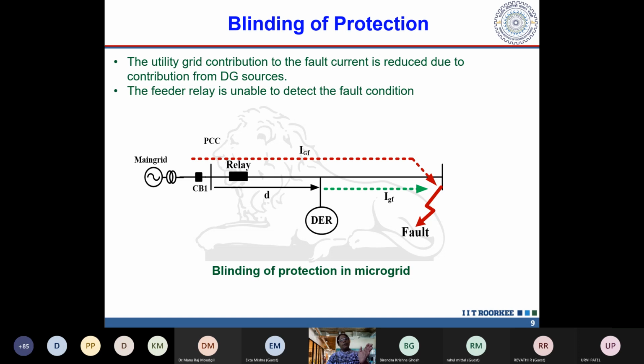And sometimes it may happen that the fault current seen by the relay may fall below the relay's current setting. So even though there is a fault, the relay has to take a decision, but it cannot. It is known as blinding, due to the presence of this DER contribution. So we have to change the relay setting. With a fixed setting, we may not take the proper decision, or we may not be able to clear the fault, or the faulty section.